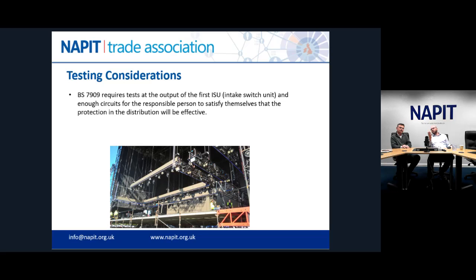We can see from the stage lighting there are many lights. So if you've got, say, 5 or 6 lights all fed from the same distribution unit, all coming up the same multi-core, all the same length, then if you get good results on one, you're likely to get the same results on the others. But I can only say that if I know that the kit is in good order and those extension leads were all checked when they turned up. So that's the recurring theme of BS 7909: the kit, when it turns up to site, must be in good order. Good.